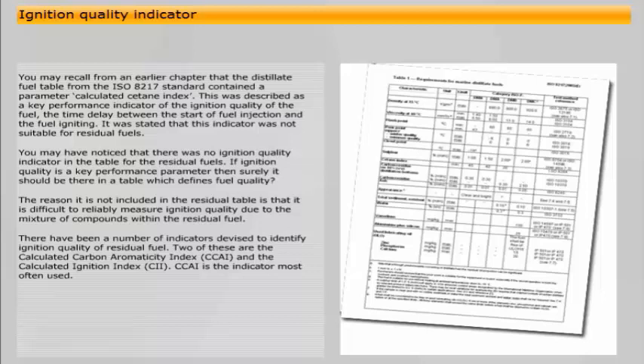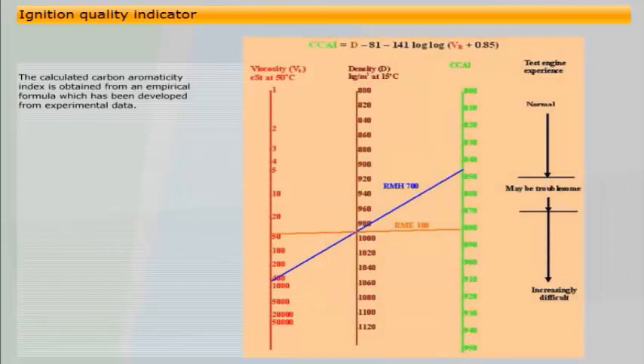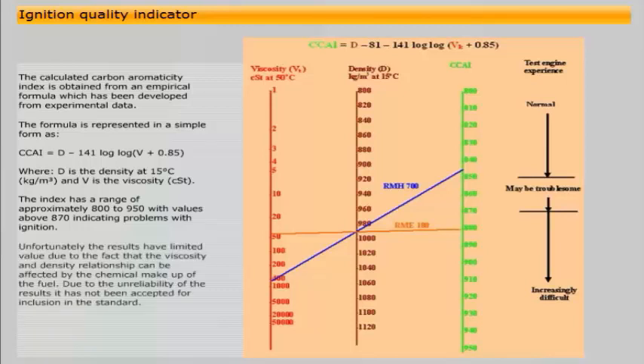CCAI is the indicator most often used. The Calculated Carbon Aromaticity Index is obtained from an empirical formula which has been developed from experimental data. The formula relating the density and viscosity of the fuel is as shown, and usually gives values in the range 800 to 950, with values above 870 indicating problems with ignition. The index has no units. Unfortunately the results have limited value, due to the fact that the viscosity and density relationship can be affected by the chemical make-up of the fuel. Due to the unreliability of the results, it has not been accepted for inclusion in the standard.